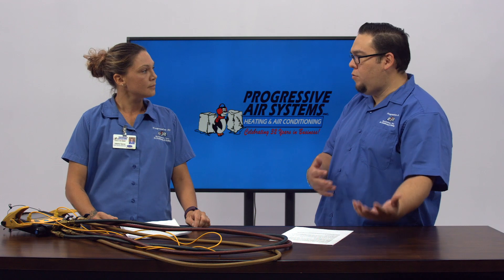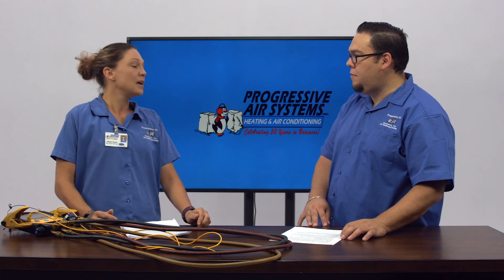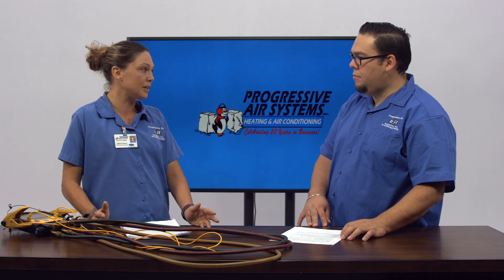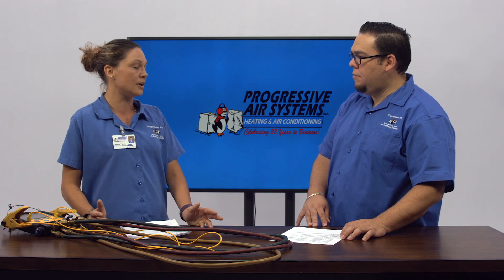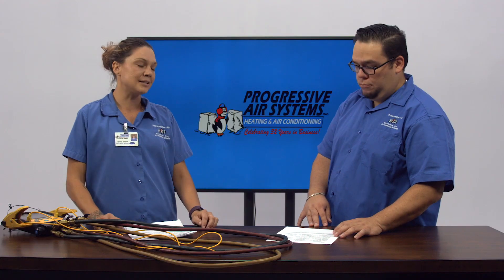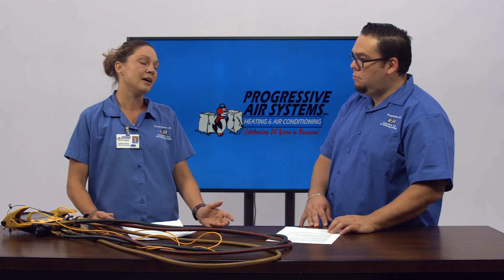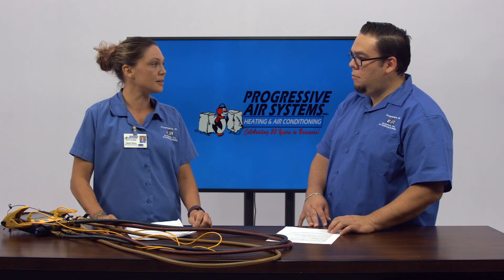And what's that process? Can it be switched out or replaced? No. An R22 system, once it's got a leak and it's determined to have a leak, that refrigerant is about double the cost of 410A. So you actually want to go ahead and look at options to replace the system. It's going to be your best bet. If you've got a leak in it, you're paying about double the 410A and then a leak repair on top of that. You just want to go ahead and replace it at that time.